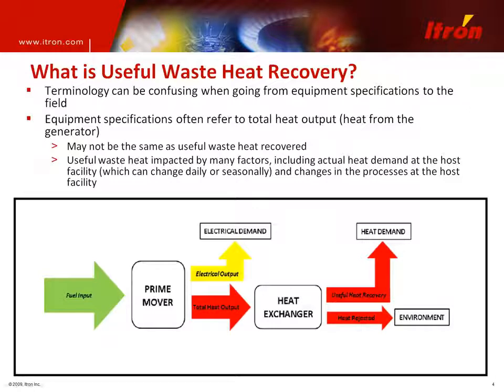And so you have a variety of folks who are going to be installing these systems. One of the things we discovered early on is that sometimes there's confusion about what's meant by useful waste heat recovery. This seems pretty fundamental, but again, you have a host and a variety of folks installing these metering systems. If you look at a typical generation equipment specification sheet, you're probably going to see that the waste heat out of that generator is referred to as useful heat. And there's nothing wrong with that. There's an assumption that that heat is going to be recovered. But that may not be really what you see out in the field.